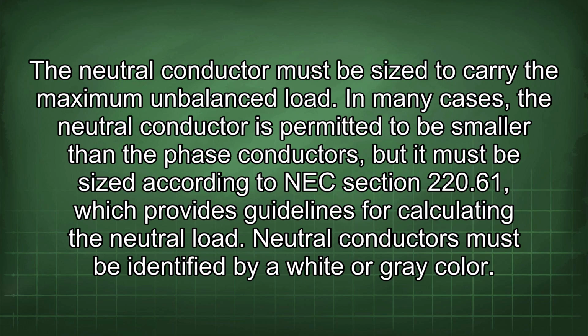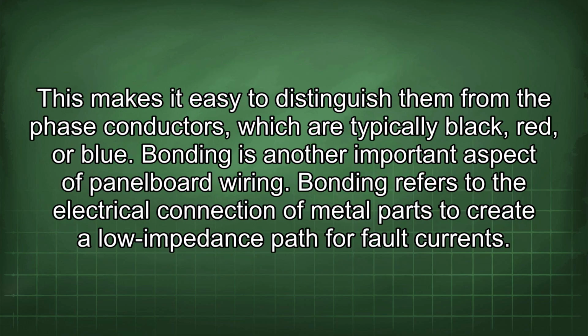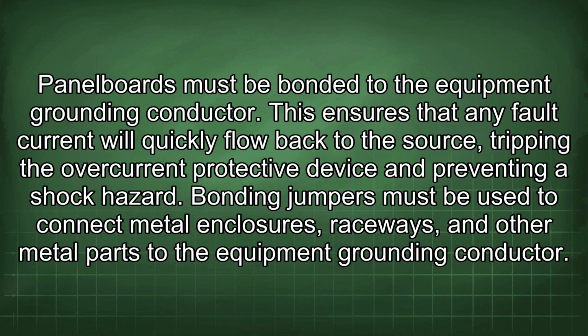Neutral conductors must be identified by a white or grey color. This makes it easy to distinguish them from the phase conductors, which are typically black, red, or blue. Bonding is another important aspect of panel board wiring. Bonding refers to the electrical connection of metal parts to create a low impedance path for fault currents. Panel boards must be bonded to the equipment grounding conductor.